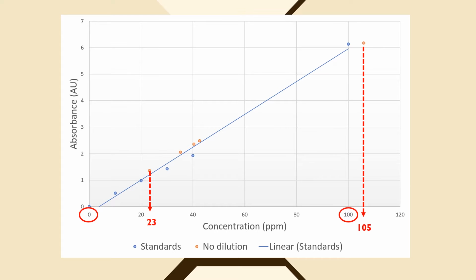If the concentration of standards were prepared differently, let's say 100 ppm as the lowest concentration, then this can lead to a non-linear response of the graph, since the concentration of samples without dilution recorded will not fall within the range of the reported line, and the data obtained from the samples will not be accurate.